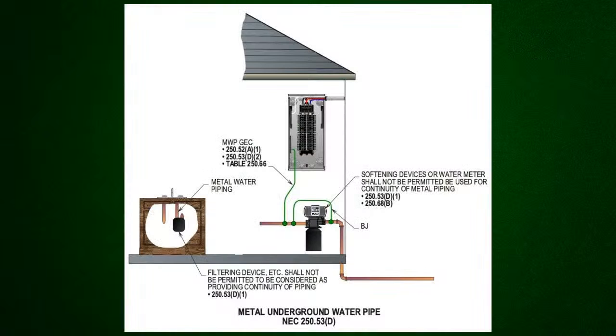Okay? Nice. So when you get over here and you look at this, this is a good illustration. We show different areas where, like the one on the left, we're showing a filtering device there and making sure that you keep the continuity and everything. Here, by the panel where it's coming in, we put a softening device in there, and we're basically just pointing out that when you're going to provide this bonding, you need to do this around the metal water pipe to provide that effective grounding path back. Okay, so it's basically making sure everything is what? Bonded. And you don't have something put in between it that will affect that effective path. And that's what it's doing right here. So when you go in and look at all this, that helps take care of it.